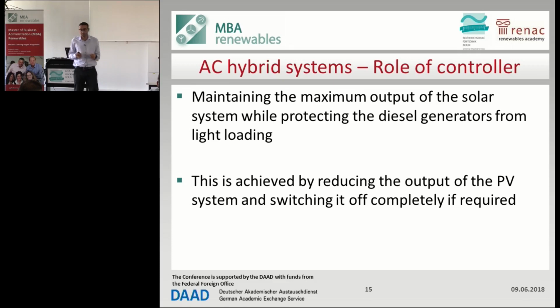Again, this was the question that Fadi asked: how is this achieved? All the PV inverters should be such that the operator of the grid is able to curtail their power. This is mandatory for all PV inverters in the world. And usually this is done in steps. The controller here will give the signal to the PV inverter to reduce its output. This is done by just switching from running at the maximum power point to any other point. And I think Lars explained this point very well yesterday. So he reduced the value of my presentation, but that's fine.